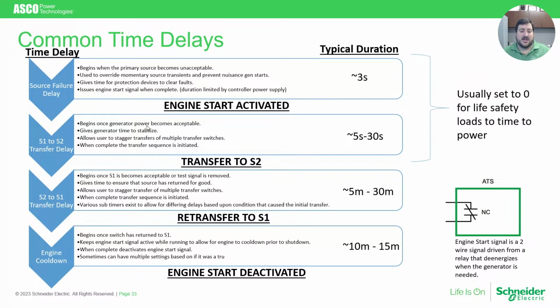Once that time delay expires, we go ahead and transfer. There's a lot of different types of transfers that can happen. And then we just wait for the utility to return. Once the utility returns, we wait another time delay to ensure it really is back and not, again, an unstable source. And then once it's returned for a significant period of time, again, user definable, we go ahead and retransfer the switch to utility power.